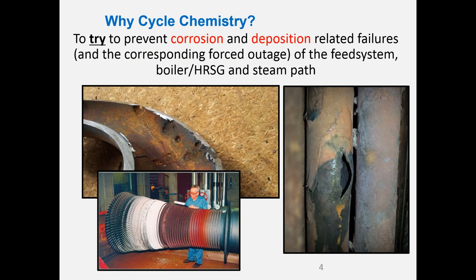So, why cycle chemistry? This is the chemistry of water and steam in any kind of boiler. What we're trying to do is prevent corrosion and deposition related failures, which invariably end up with what we call a forced outage — where the plant is shut down and unable to produce steam or electricity. You want your plant to operate as and when required, without any unplanned forced outages. You want to plan your outage around your process.